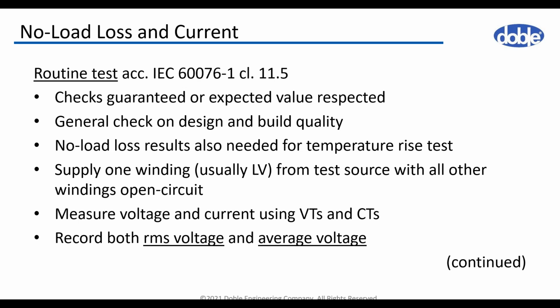So, how do we perform this test? We have one winding which is energized from the supply, and the other windings are left open. The measurement is performed using measuring transformers and power analyzers, similarly to the load loss and impedance. For convenience, the supply is usually applied on the low voltage winding in the test field.